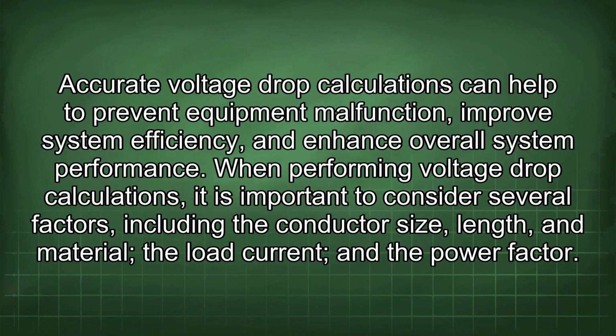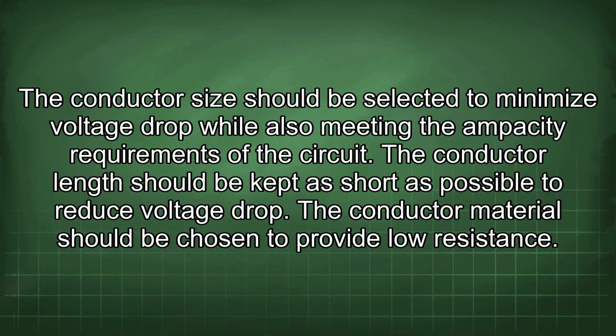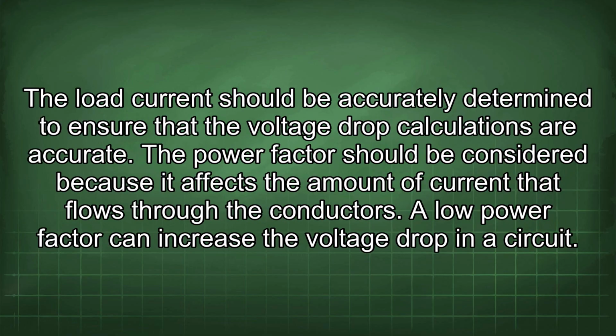When performing voltage drop calculations, it is important to consider several factors, including the conductor size, length, and material, the load current, and the power factor. The conductor size should be selected to minimize voltage drop while also meeting the ampacity requirements of the circuit. The conductor length should be kept as short as possible to reduce voltage drop. The conductor material should be chosen to provide low resistance. The load current should be accurately determined to ensure that the voltage drop calculations are accurate.